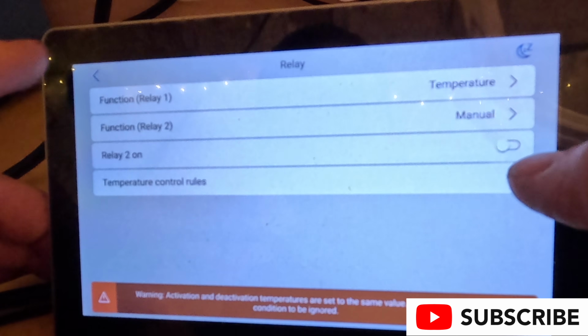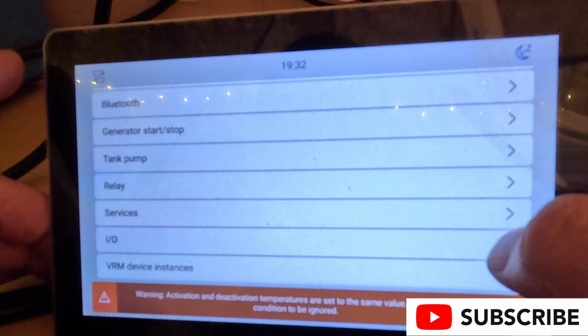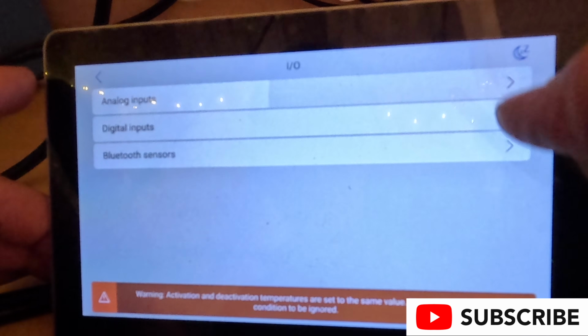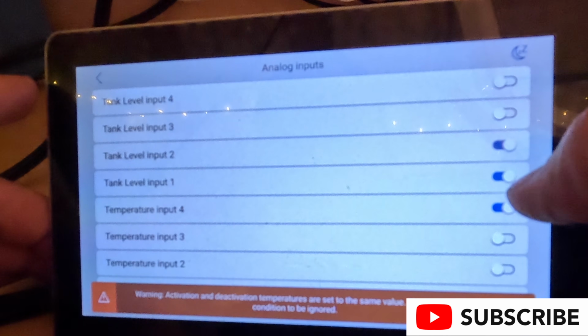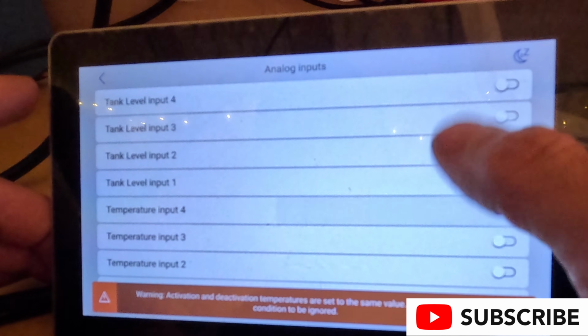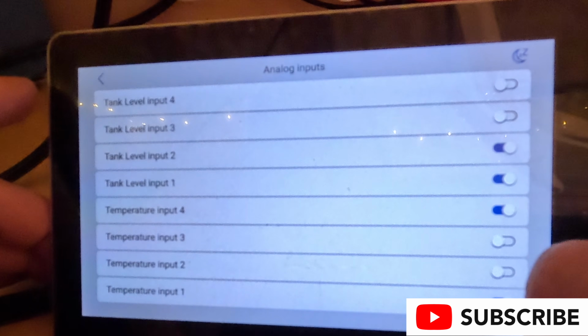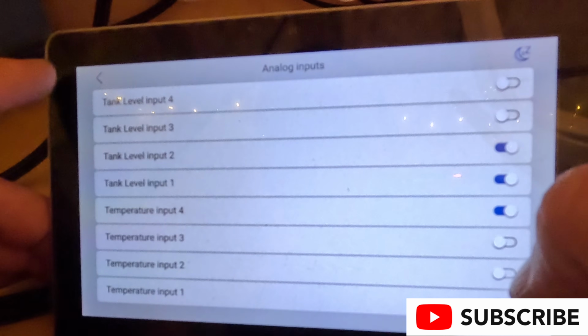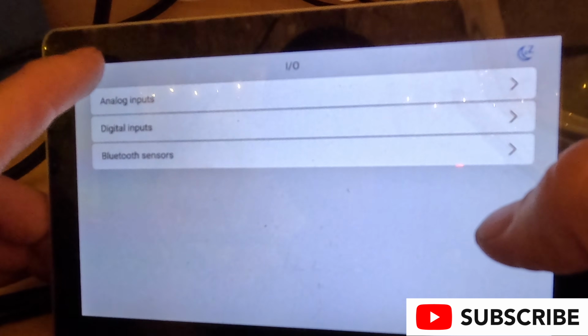Now we can go into our I/O menu, analog inputs, verify one more time that our temperature 1 is toggled on. Accidentally toggled temperature 4 on too, but we'll just toggle it on and off just to make sure it's being read as on.